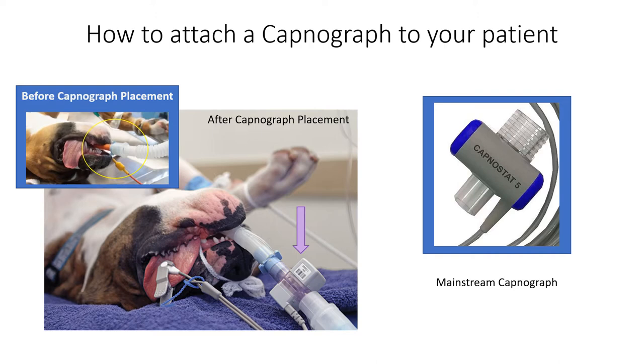As you can see in the yellow circle, an endotracheal tube is inside your patient, the breathing tubes are hooked up to the anesthetic machine, and the breathing tubes plug right into the endotracheal tube. A capnograph can only be attached one way, in between the breathing tube and the endotracheal tube. The wider end is over the endotracheal tube and the narrower end is into the breathing tubes.